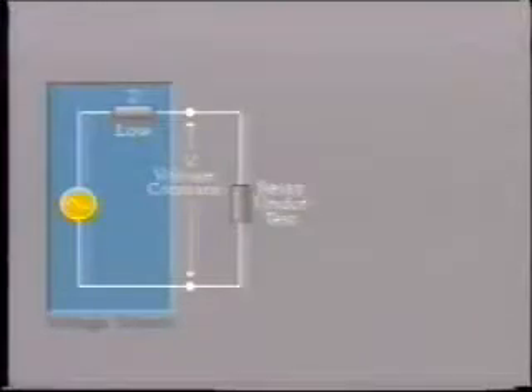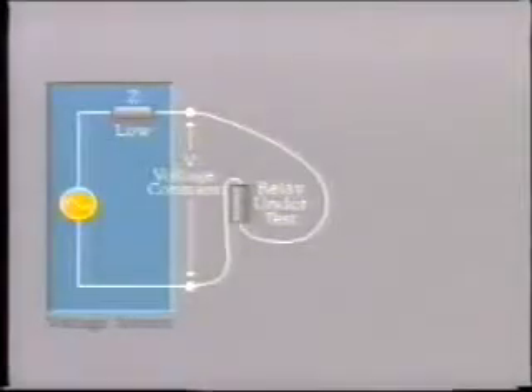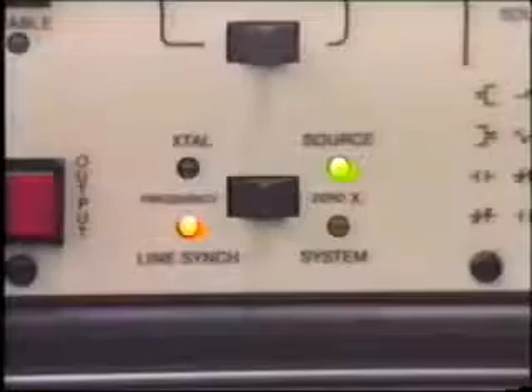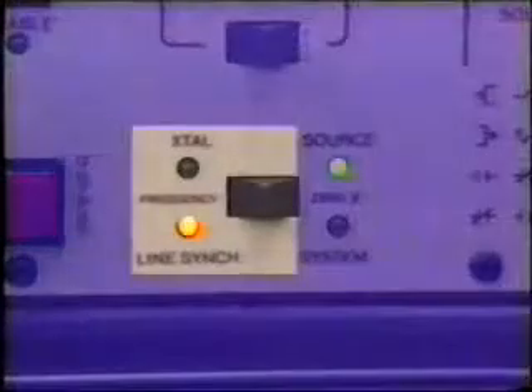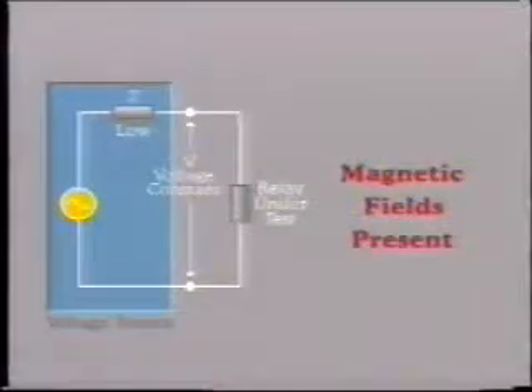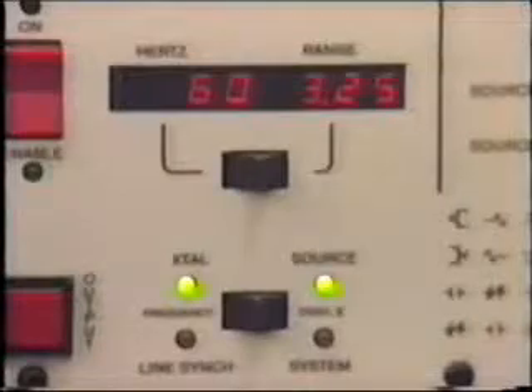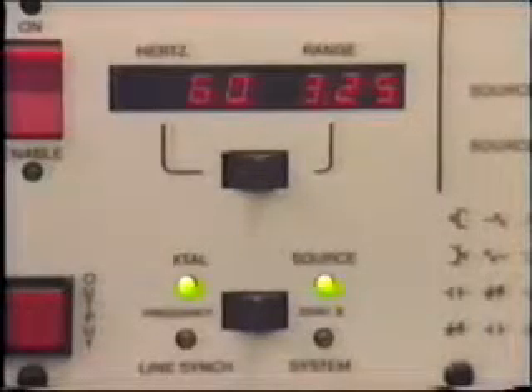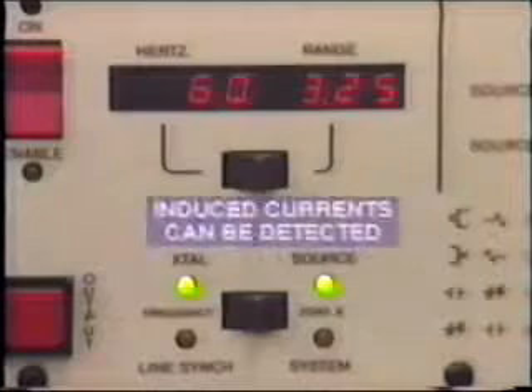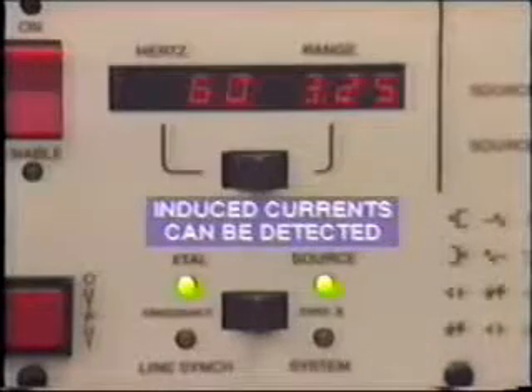To verify that no appreciable error is being caused by the induced current, repeat the same test with all signals rotated by 180 degrees. We are still using line synchronization. If the results are the same, then the interference is negligible. If not, a way to reduce or eliminate the interference must be found. In any case, choosing the crystal as the usual synchronizing mode allows you to detect the presence of induced currents and take whatever action is required.